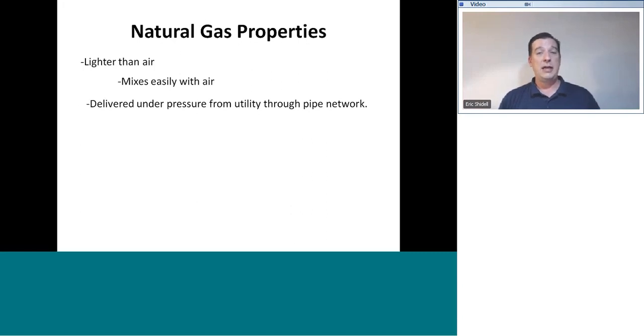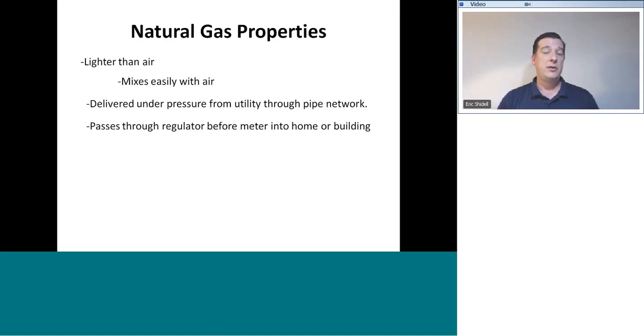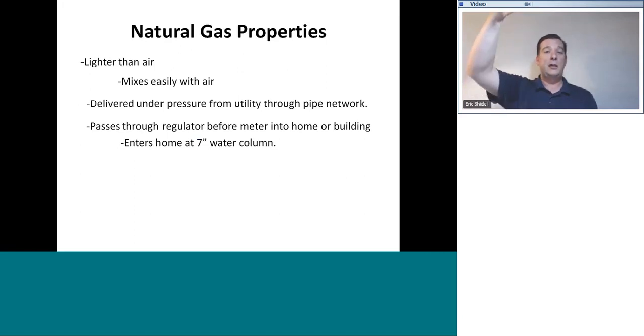Natural gas is delivered to its final point of use under pressure from a utility provider through a network of pipes, generally underground. It will pass through a pressure regulator and then a meter to count the amount of gas that's being used before it goes into a home or a building. If it is a residential application, it is going to enter the house in general, and all across the country, at a pressure of 7 inches of water column. If you're not familiar with the measurement of inches of water column, inches of water column is a measurement of pressure. And it means the height that that pressure will push a column of water.